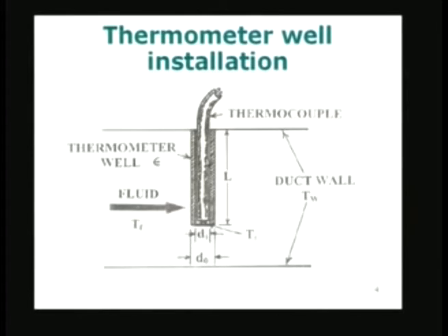Again, as we saw in the previous case of solid material, the length of the immersion is going to play an important role. The other things which are going to play an important role are the physical size, that is di and d0, and also the thermal conductivity of the material of the well. These are going to be important parameters. That means the physical dimensions di and d0, which are geometric parameters, the length of immersion is also a geometric parameter, and then we have the thermal conductivity of the material of the well.